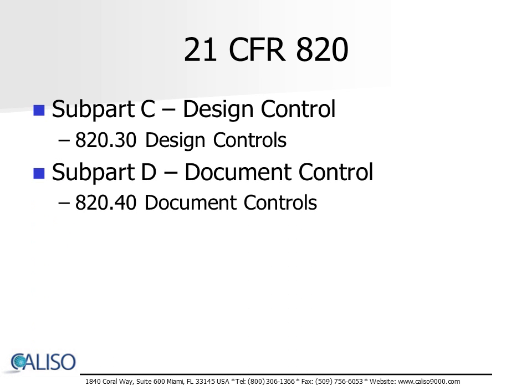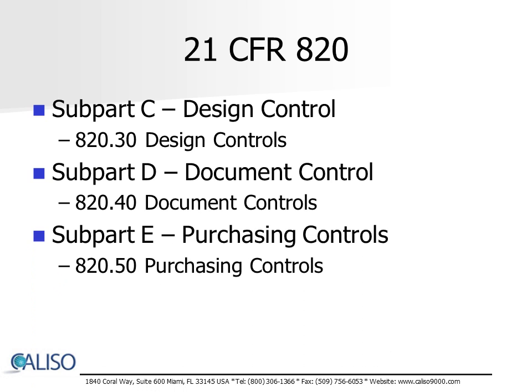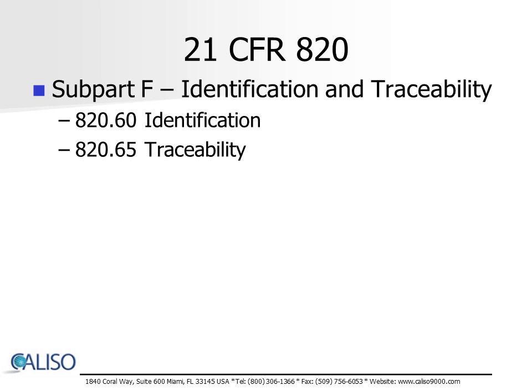Subpart D contains the requirements for document control, or how your documents are created, revised, and managed. Subpart E contains the requirements for purchasing controls, which includes supplier evaluation. Subpart F contains the requirements for identification and traceability. Identification and traceability for medical devices is critical to ensure a quick and effective recall, if necessary.